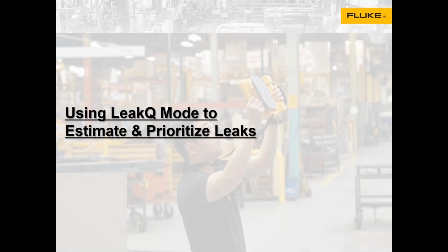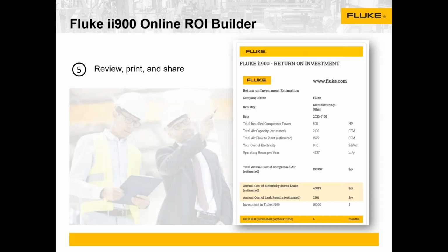And I would just highlight that, you have the 500 horsepower there, that even with 500 horsepower, it's about $150,000 a year of energy. So if you can get some portion of that in savings, and the Department of Energy has clearly showed that most facilities have about a fourth of that in loss. So there's a big opportunity.